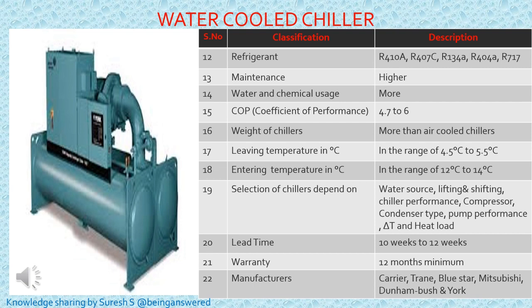Another parameter we need to know in the chiller is the leaving temperature and the entering temperature. The delta difference should not be more than 7. Those are the parameters we need to look into. Leaving temperature means the output from the chiller. On water cooled, it will be 4.5 to 5.5 degrees centigrade. After the water enters the AHU, it comes back to the chiller as input. That temperature will be around 12 to 14 degrees centigrade, if the pipe insulation and everything is good, then we will get this range in the actual measurement.